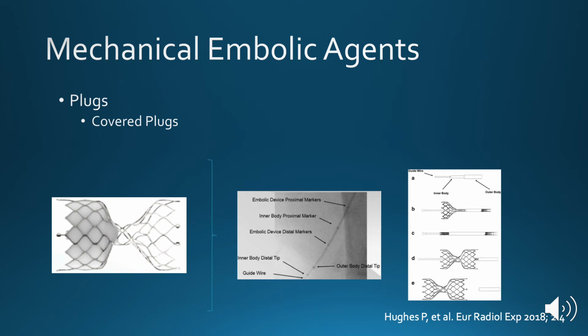One of the challenges in using any of these plugs is understanding the markers that you're seeing under fluoro before you deploy the device. In this particular case, there are at least 3 markers along the length of the plug, as well as a marker at the tip of the delivery catheter, which is a proprietary system that goes over an 018 wire. Once you retract the delivery catheter and start delivering or deploying the plug, you do have the option to retract the plug back into the catheter until you deploy at least the first half of the plug.